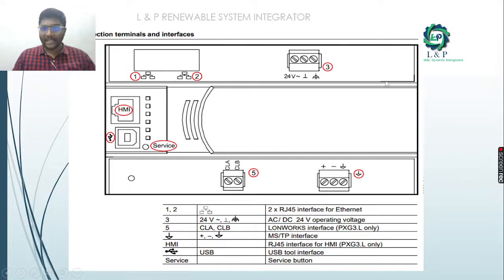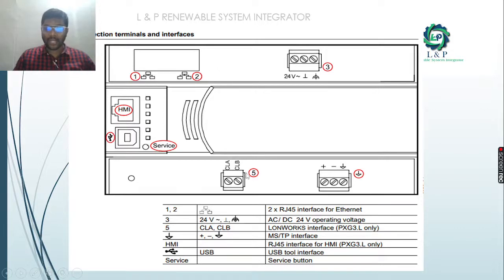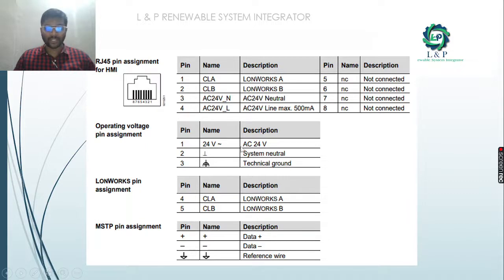Looking at the connection terminals: the power terminal takes 24V AC. There are two RJ45 jacks for Ethernet connections, a terminal for the MSTP interface, and a terminal for the LonWorks interface. To reset the router to factory settings, press the service button. The HMI port and the LonWorks interface are available only on the PXG3L model. Both models have MSTP and normal Ethernet RJ45 pin assignments.